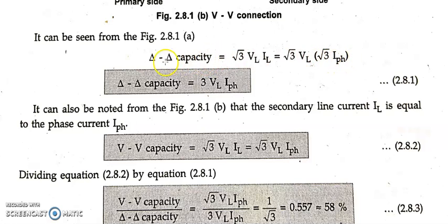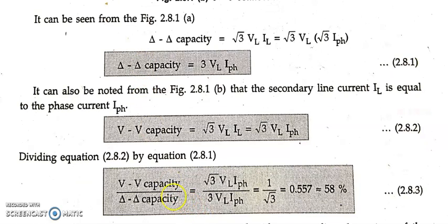Why? Because current was dividing in the delta connection of the transformer. But here in VV capacity, current is not dividing. So whatever IL is there, the same will be I phase. So IL is equal to I phase, and I'm going to replace IL by I phase. Now what I'm going to do is divide 2.82 by 2.81, that is VV capacity by delta capacity. VV capacity formula is root 3 VL I phase, whereas delta capacity is 3 VL I phase. Yes.